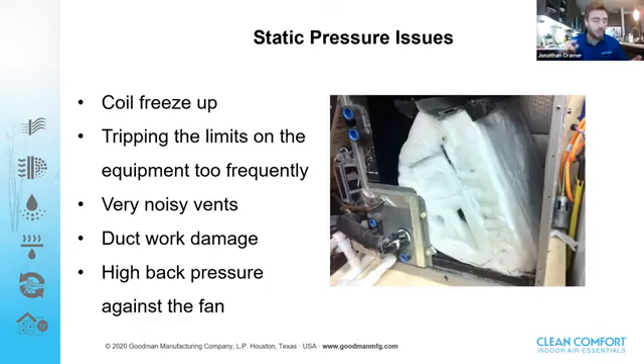The coil can freeze up. You're going to be tripping your limits. Obviously it's going to be super noisy. It's going to be damaging the ductwork. There's just a lot of issues when it comes to static pressure. So this is just what happens when we don't have a way to regulate static pressure.